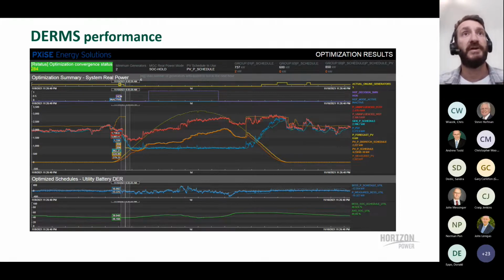That's a collaboration between the DERMS schedules every 5 minutes and then the PXiSE MGC, mopping up the difference between any real or reactive power excursions within that 5-minute interval.